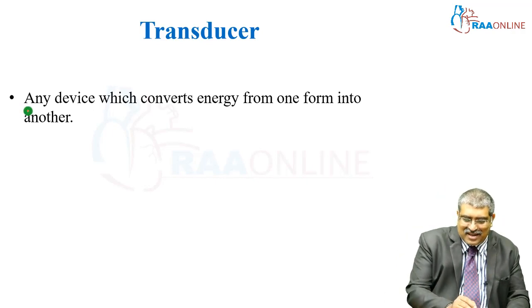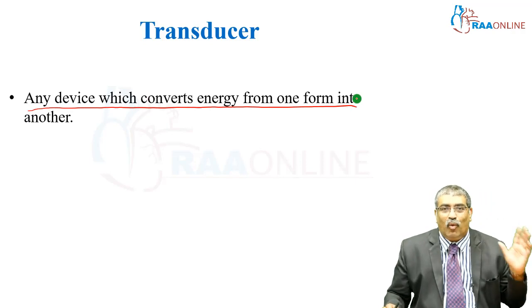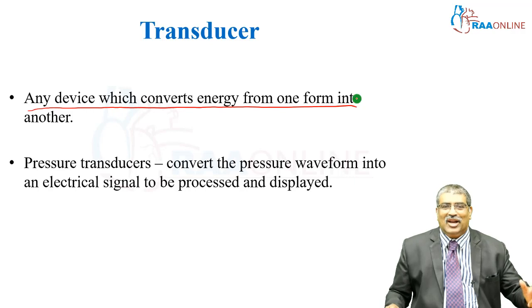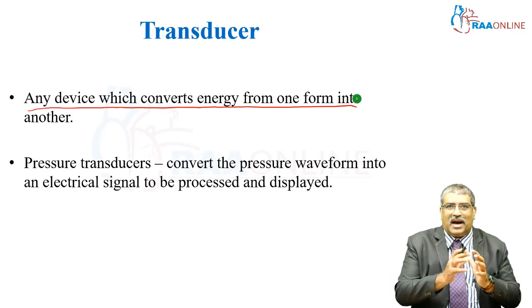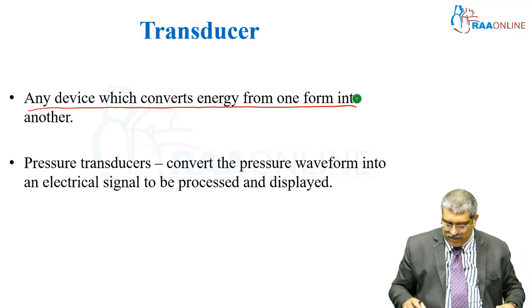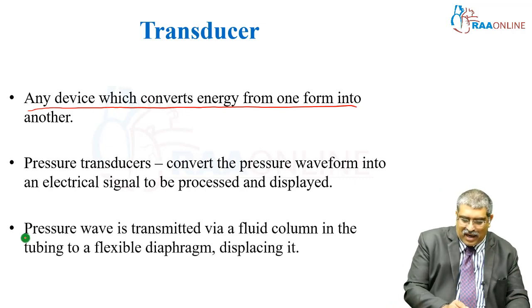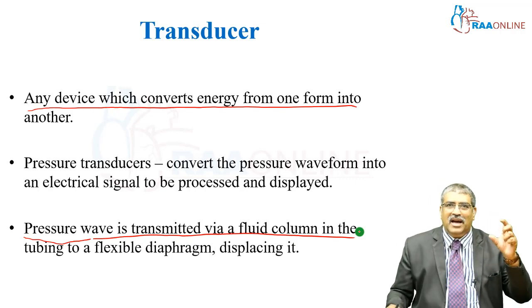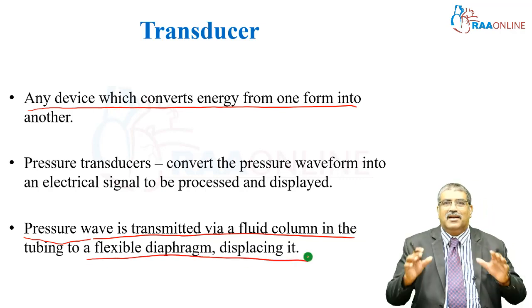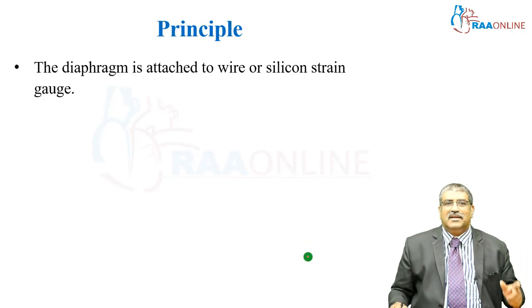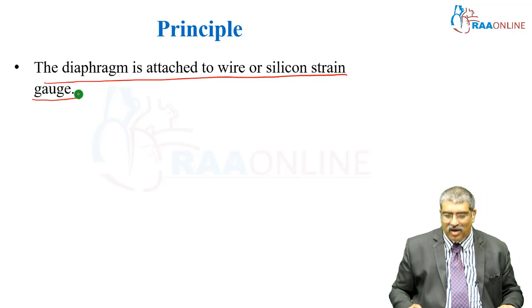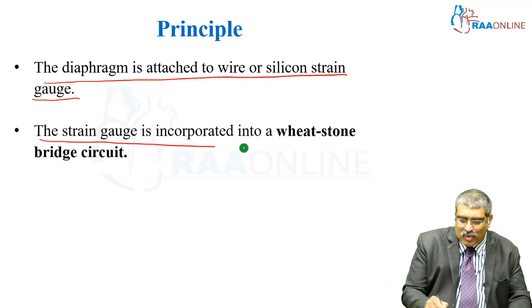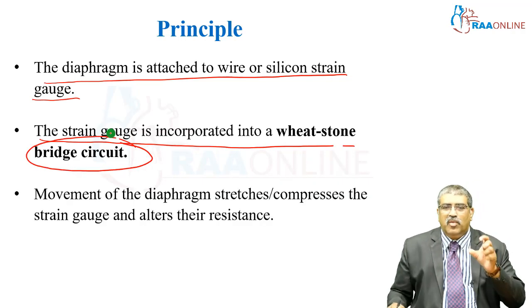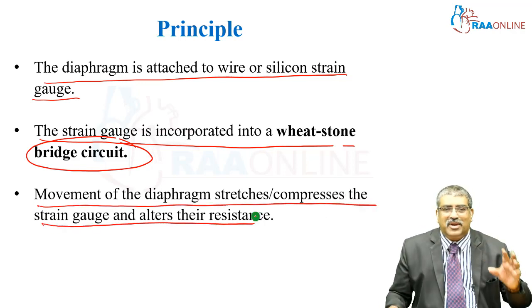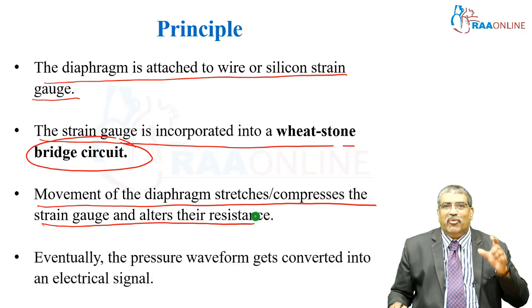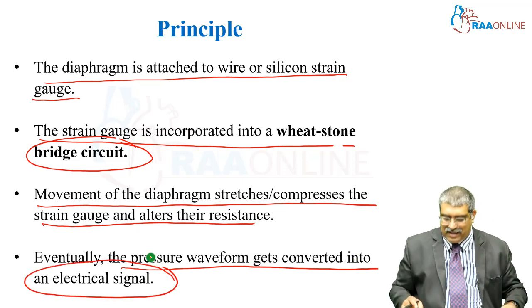What is a transducer? A transducer is a device which converts energy from one form to another. Here, it converts mechanical into electrical energy. What was that mechanical energy? The mechanical contraction by the heart, which is exerted as a pressure, is converted to an electrical signal. This pressure wave is transmitted from the artery to the transducer via a fluid column in a tubing, and there is a flexible diaphragm sitting there in the transducer which is altered. The diaphragm is attached to the wire or silicon strain gauge. This strain gauge is incorporated into what is called a Wheatstone bridge circuit. The movement of the diaphragm stretches and compresses the strain gauge and alters the resistance. Eventually, the pressure waveform gets converted into an electrical signal.